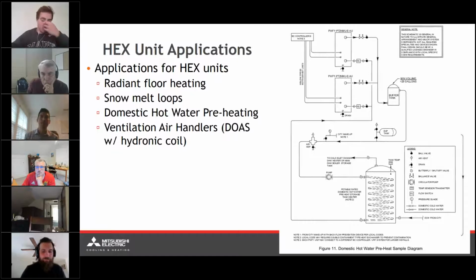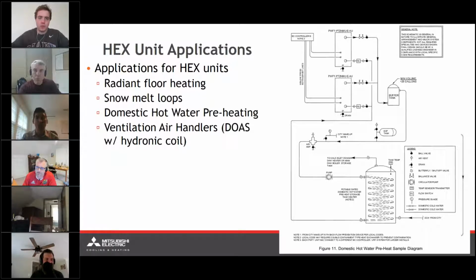Other options: potentially, we have the option of tying into a domestic hot water system for preheating. So we want to make sure that we're factoring in peak domestic hot water draw when focusing on an application like this. And considering the peak domestic hot water draw, the selection of the primary domestic hot water system can ultimately be determined. Typically, the capacity of the hot water heater could be adjusted based on the amount of hot water storage used in conjunction with the peak heating rate of the domestic hot water heater. All that said, we're trying to ultimately draw down the amount of gas that we're going to be burning to create this hot water. So in this particular example, it's going to be supplemental heat in order to pull down the peak heating draw for the domestic hot water system.